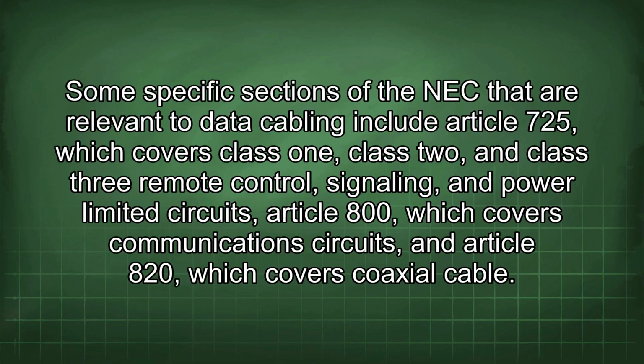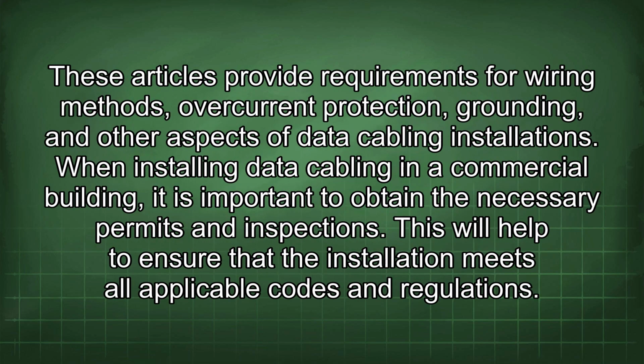Some specific sections of the NEC that are relevant to data cabling include Article 725, which covers Class 1, Class 2, and Class 3 remote control, signaling, and power limited circuits, Article 800, which covers communications circuits, and Article 820, which covers coaxial cable. These articles provide requirements for wiring methods, overcurrent protection, grounding, and other aspects of data cabling installations. When installing data cabling in a commercial building, it is important to obtain the necessary permits and inspections. This will help to ensure that the installation meets all applicable codes and regulations.